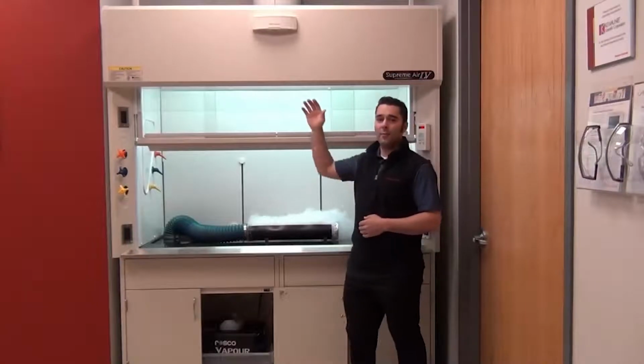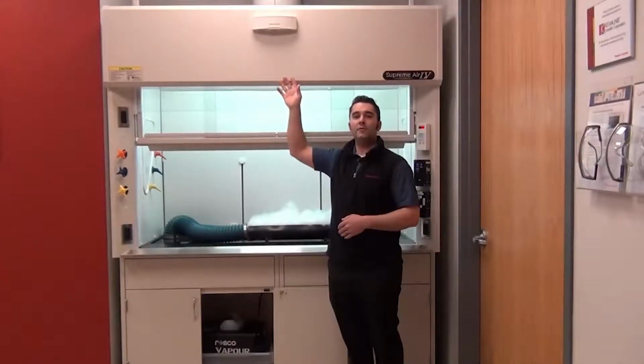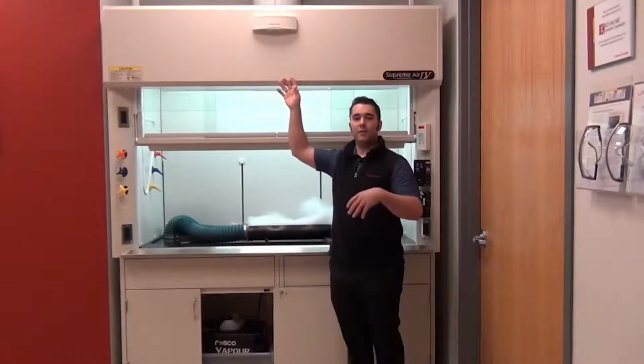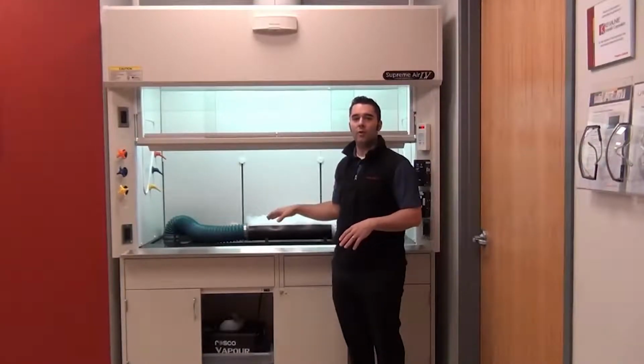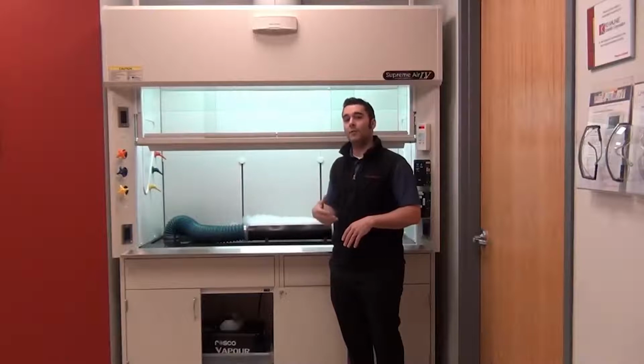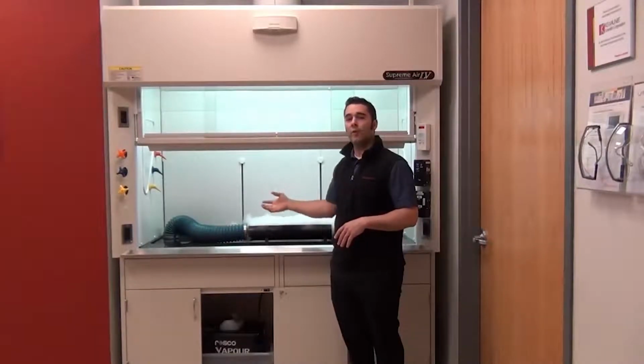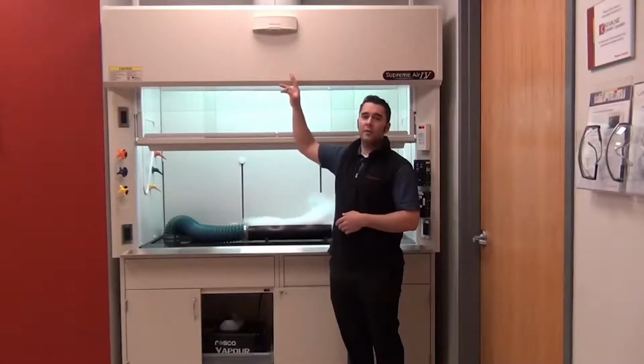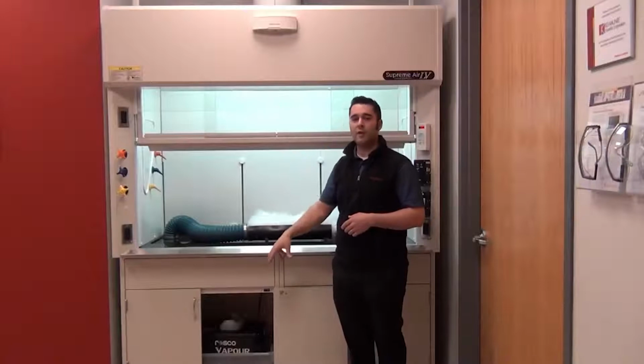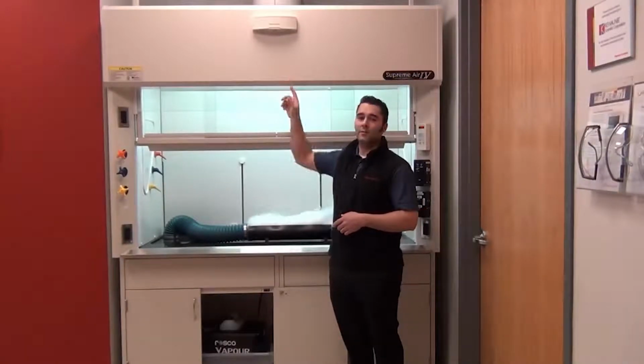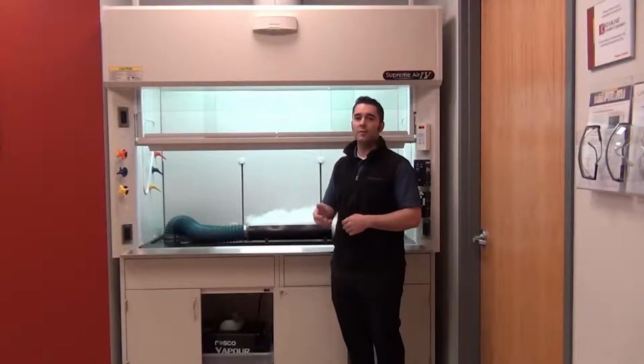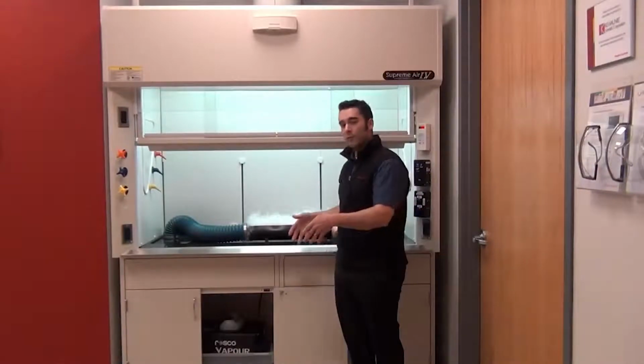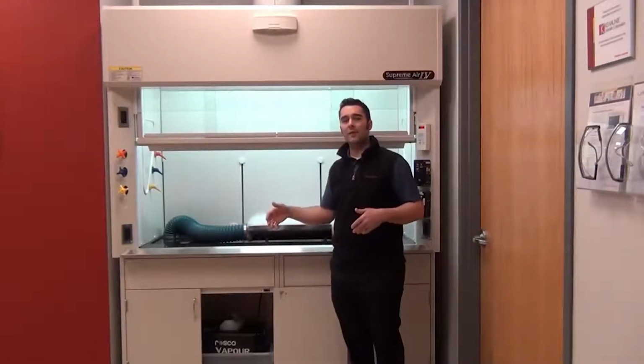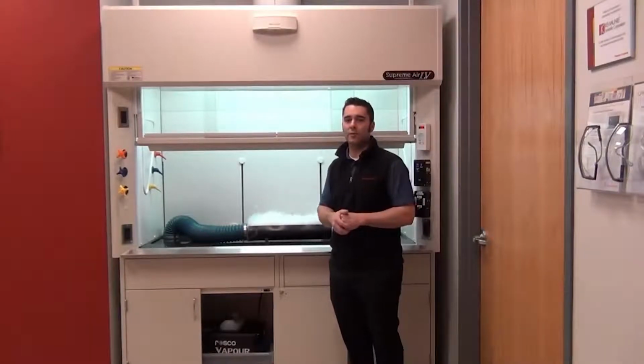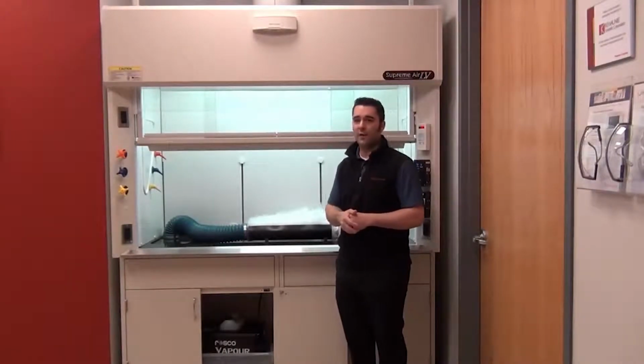The other nice thing about this particular device is if you're using this in low light conditions, so if I need to shut the ambient light in the room off and I'm still working in the fume hood, or in the case where I'm doing animal testing and I have to use something like a red light inside of the fume hood so the animal thinks it's nighttime, the infrared generators that we have in this will actually project down onto the floor, and this device will actually work in pitch black as well. So it's variable based on the amount of room you need in front of a fume hood and the sensitivity of it, but it will also work in low light conditions as well. So that's one way that we save money.